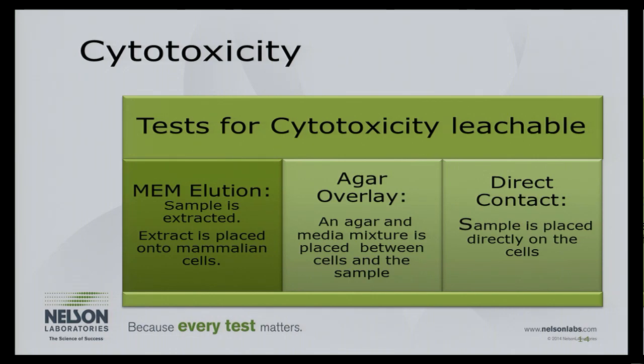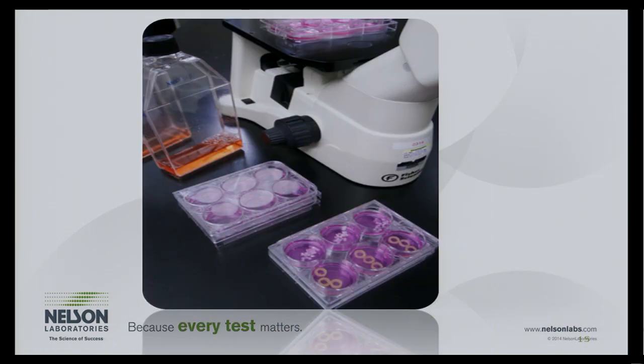For cytotoxicity, the MEM elution is the historic, easiest, and quickest test we run. The cytotoxicity test uses L929 cells — mouse fibroblast cells. These are the most common cells used because we have the most history with them and can compare scores sample to sample. You might consider a clinically relevant cell line, like ocular or neural cells, but L929 is preferred because of the extensive knowledge base. We grow cells in flasks where they adhere, then break them apart and seed them in six-well plates.